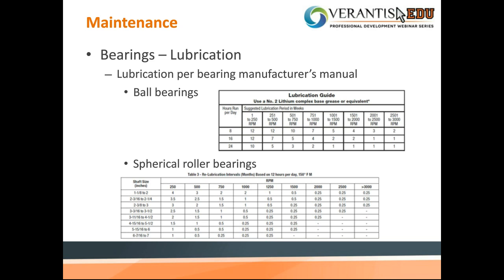If I've got a bearing that has, let's just say, a 1 7/16 bore size, and it's running 24 hours a day. So what we'll do, we'll look at 24 hours a day. Typically, we know the fan is going to be running at, let's just say, 1,200 RPM. We know that it should be inspected once a week. So that's typically how that chart is laid out. Like I said, that should be in the operating maintenance manual once you get your fan, and definitely refer to that as to how often you should be lubricating the bearings.